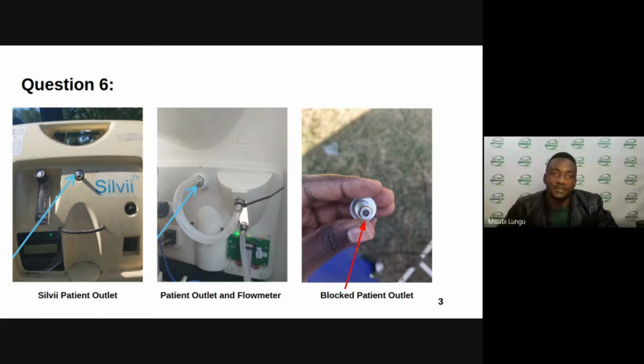Thank you very much, Efa, for that explanation. So this is a question that I was referring to at the beginning. Masofa gave us an update on the issues that he had, and it was something similar to this. The only difference is this was at the patient's outlet spot, but Masofa's situation was an issue with the one-way valve. So these things do happen. There are some insects that don't take time. As long as they see an opening somewhere, they get in there and then they build a nest, and that just messes up the machine. So always be sure to be thorough when checking for these blockages.